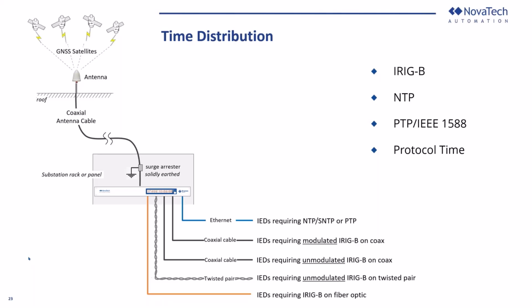In IRIG-B, you have the capability of further distributing this using a T channel. You could further distribute time by rack, and this has to be calculated based on how many devices you can distribute over IRIG. So time is important, and we have to ensure all the devices in the substation are synced to some time reference for all these applications.